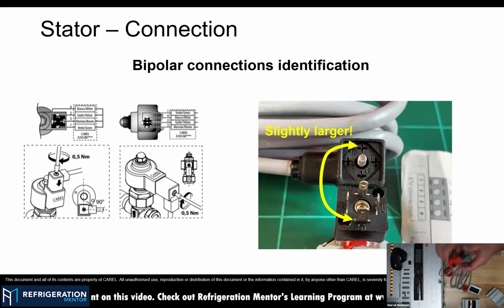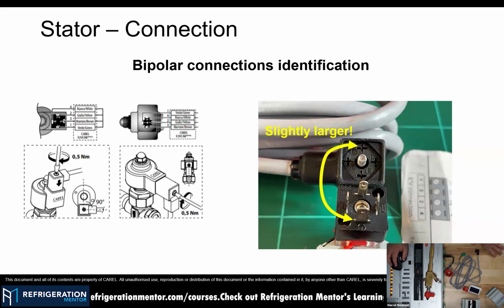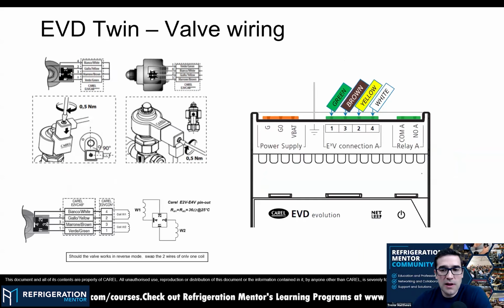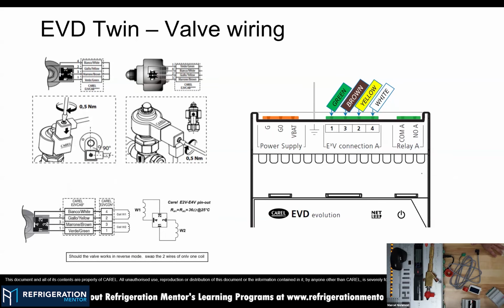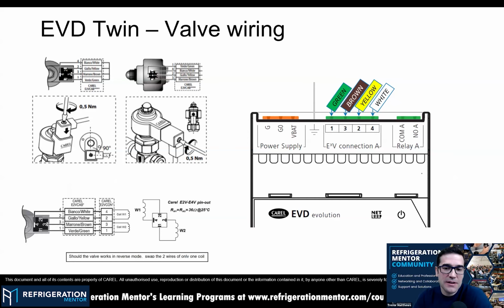If you install with this new model of coil, the cable will always go towards the bottom, and if you have the old model, it will always go towards the L of CAREL on the valve. So it's, let's say, an easy way to identify how to install it. It shows the proper way to install the cable to the coil. What a coincidence! All this is in the manual. Yeah. All of it is in the instruction manual. You've got to take a look at it and follow that.